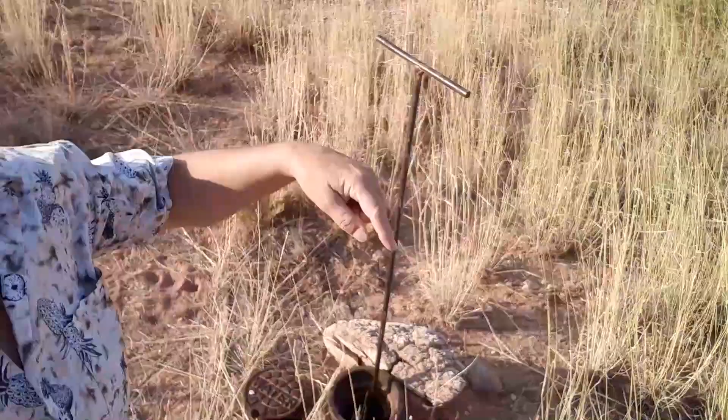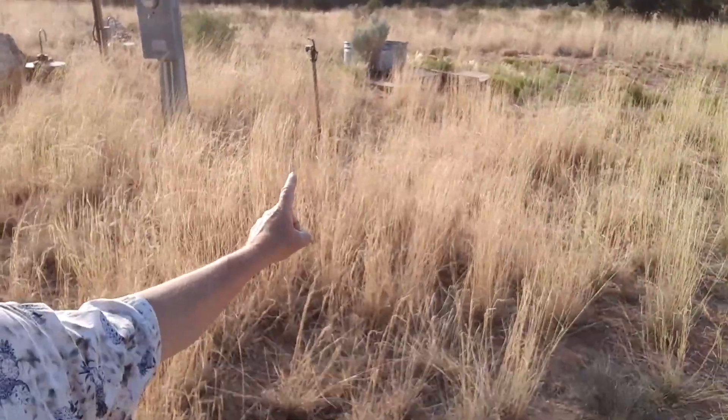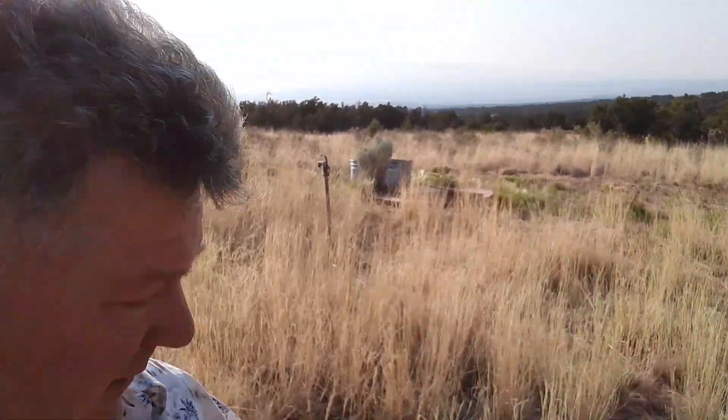After 24 hours I just got back down to the well site. What we were doing in the last 24 hours was testing from the mains back to the pump house to see if there was any pressure leak. Everything looked good — perfect, no change in pressure. So now I'm going to go down and test the lower trunk line, which goes through our property and a couple others. I'm opening it up and I'll be driving down there to check it in just a moment.